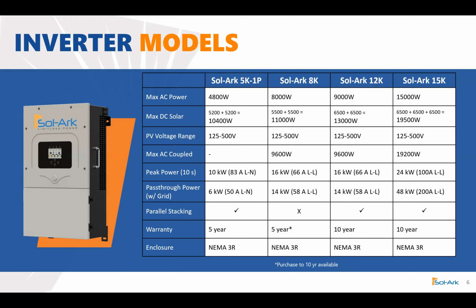We can also do something called AC coupling. I'll touch a little further on that, but just to touch on that subject, you can connect micro-inverters or maybe another string level inverter that doesn't have the ability to add energy storage, and you can run it through our system and we'll add the controls for it and provide that signal off grid. Our inverters are also known for having a higher peak power. So maybe the homeowner has a large air conditioning unit, maybe a large well pump that's 2 or 3 horsepower. Well, as long as it's within our peak power range, we can provide a 10-second peak power to make sure those products and appliances will start up appropriately.